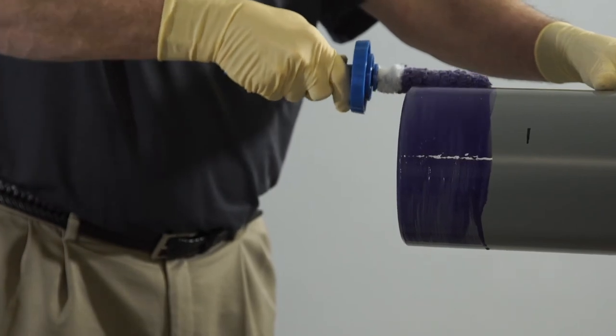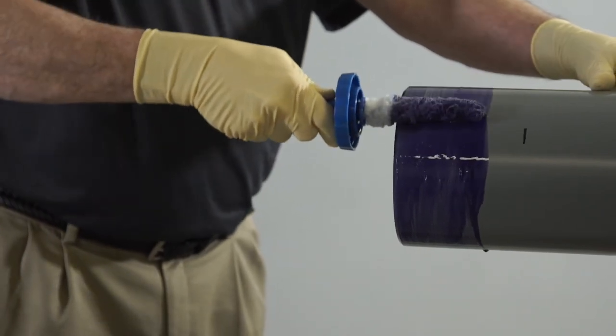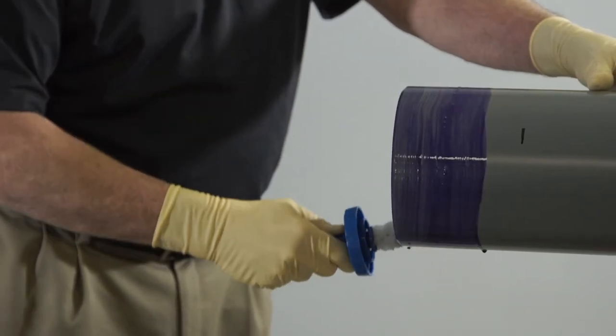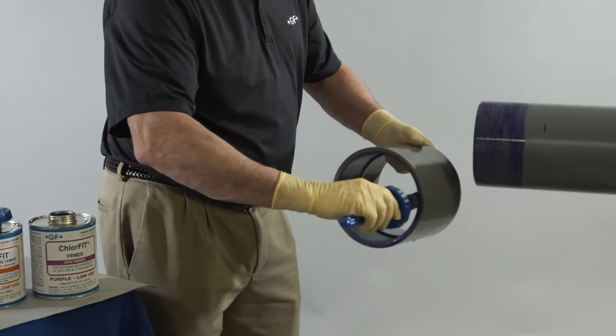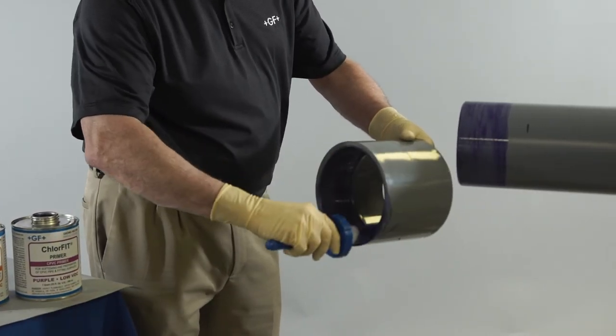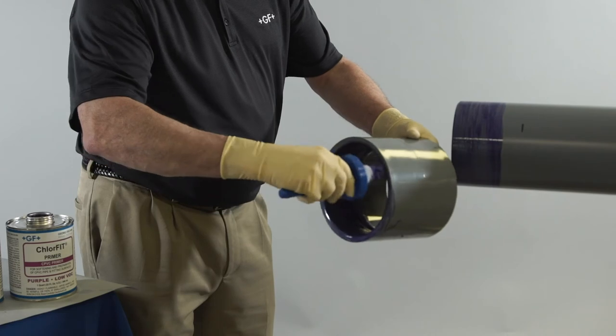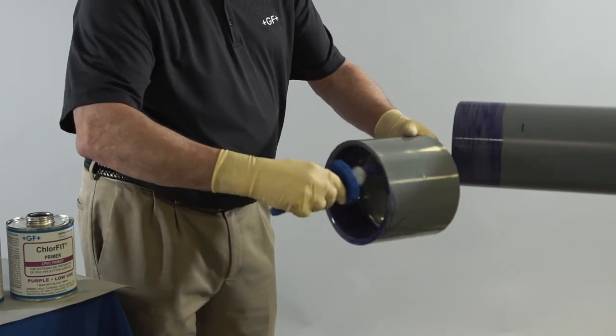Next, aggressively apply the primer to the end of the pipe to a point one half inch beyond the depth of the fitting socket. Apply another coat of primer to the socket. Do not allow the primer to run down the inside of the fitting or puddle at the bottom of the pipe.